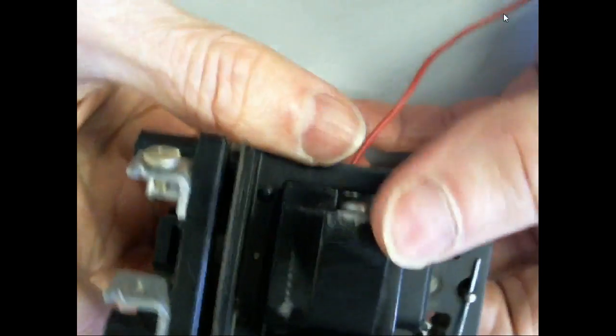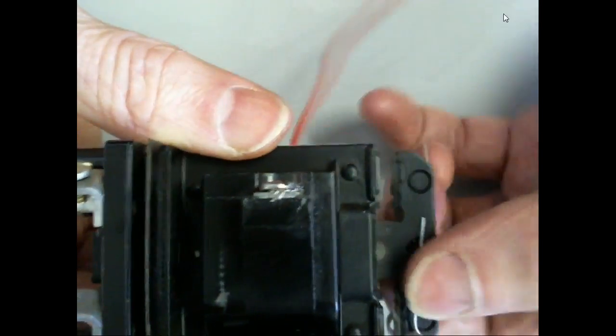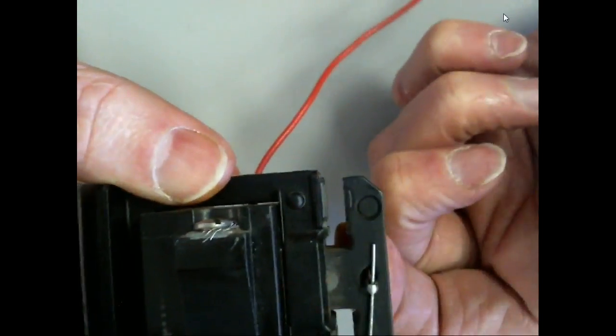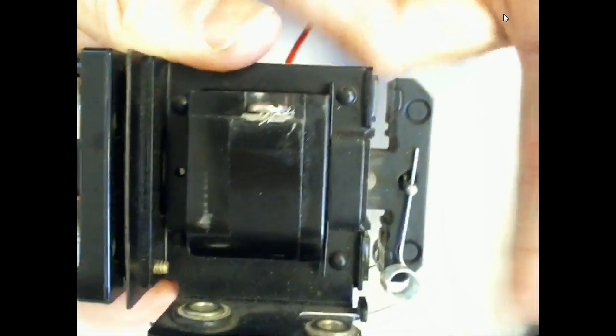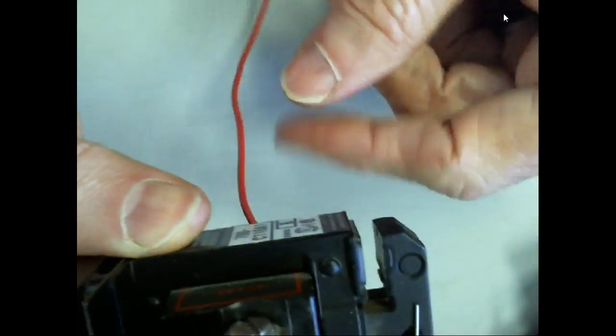So here's my solenoid right here - this is what they're showing you. Here's this guy right here, some people call it a plunger, but it's technically called the armature. When I put power on it, it's going to suck that in, right? Can y'all see that? Now this has a spring on it, so I can mount this relay any way, and the spring brings it back to its unenergized position.